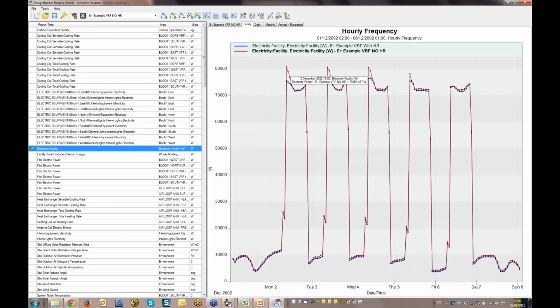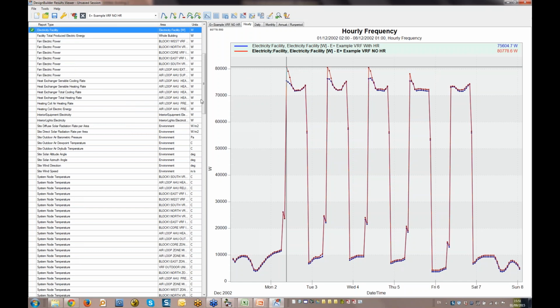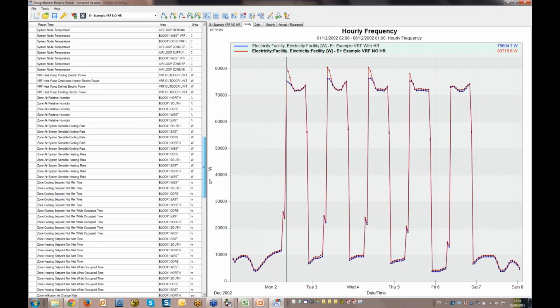The results clearly show that heat recovery is beneficial, particularly at startup first thing in the morning, when there's the greatest differential between the core cooling load and the perimeter heating loads. So that basically covers all the main points relating to modelling VRF systems in DesignBuilder and using the Simulation Manager and Results Viewer to analyse results.